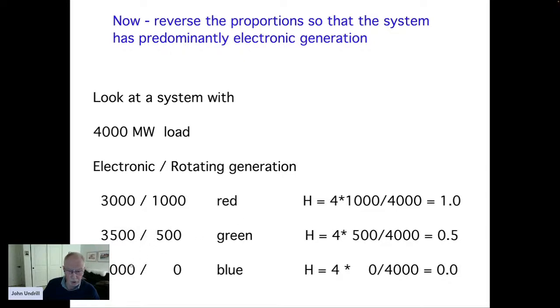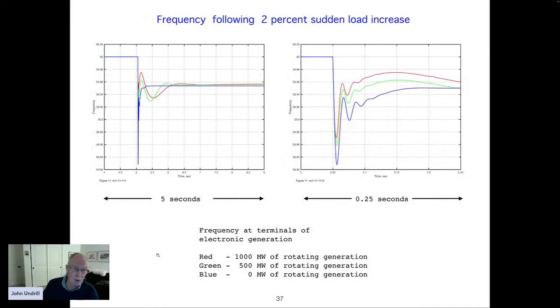Or let's go to the extreme and say, could we control this thing if it was 100% electronic? Let's consider the same event. So a 4,000 megawatt system, an 80 megawatt sudden unbalance of load and generation, and look at what happens. Well, here's what happens. And it doesn't look radically different from what happened in the other case, except where we were looking at a span of 50 seconds with the conventional system, we're now looking at a span of 5 seconds. The event occurred from here to perhaps here, with the nadir frequency occurring at 5 seconds with the all rotating system. Now the event occurs and the thing is settled out within a quarter second.